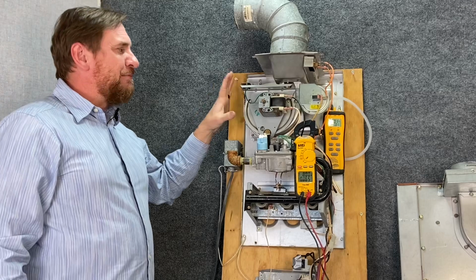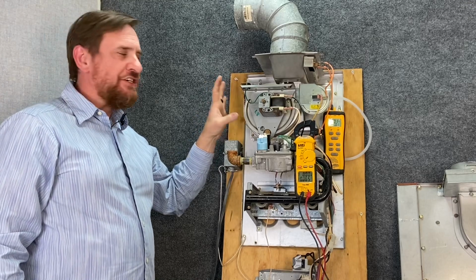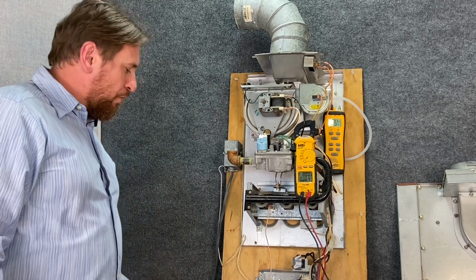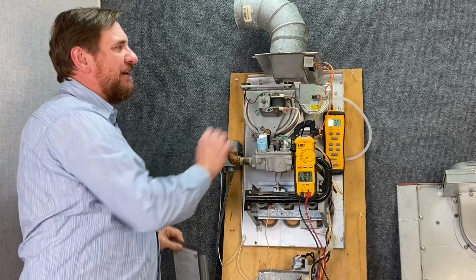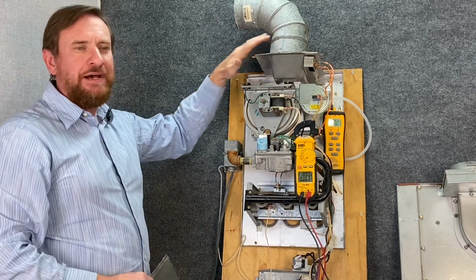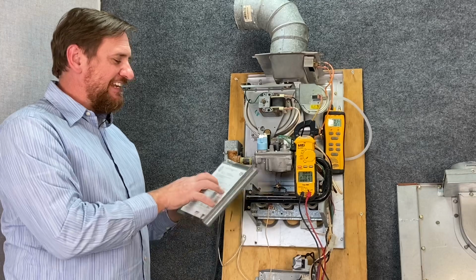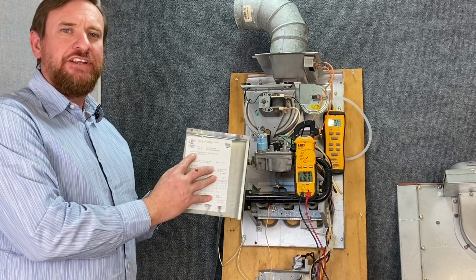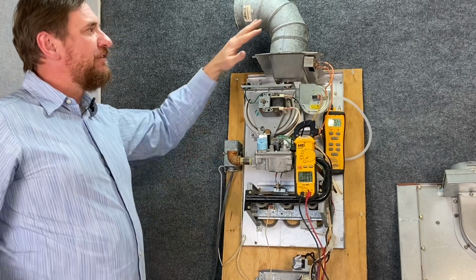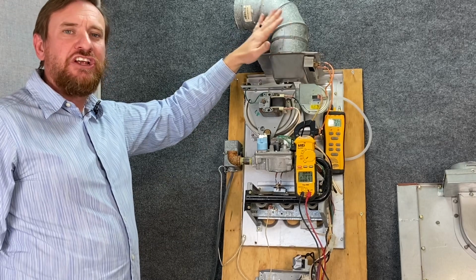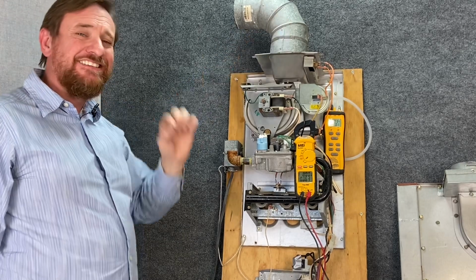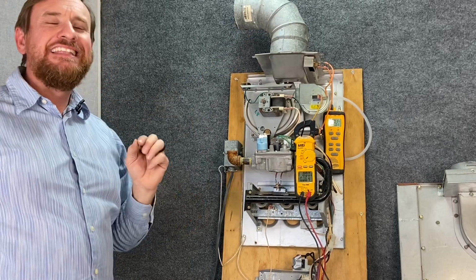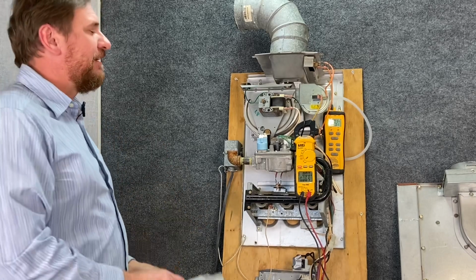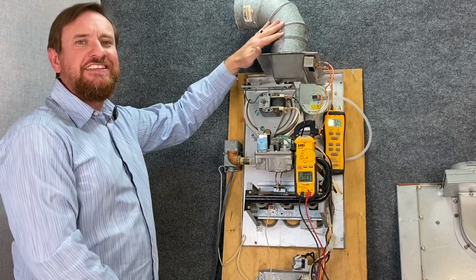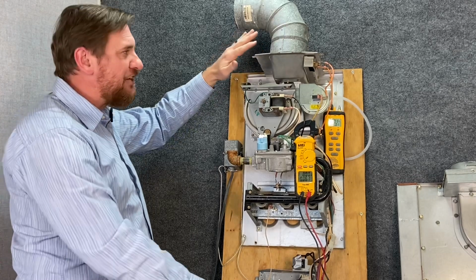But I want to talk about some other very important pieces of information for this inducer draft motor. One of those is this style right here. We have a double wall vent pipe. This gas furnace is a category 1 gas furnace. A category 1 gas furnace means this is negative pressure, non-condensing. That's essential. Category 1, negative pressure, non-condensing. That means this gas furnace is natural draft. It's naturally drafting out.